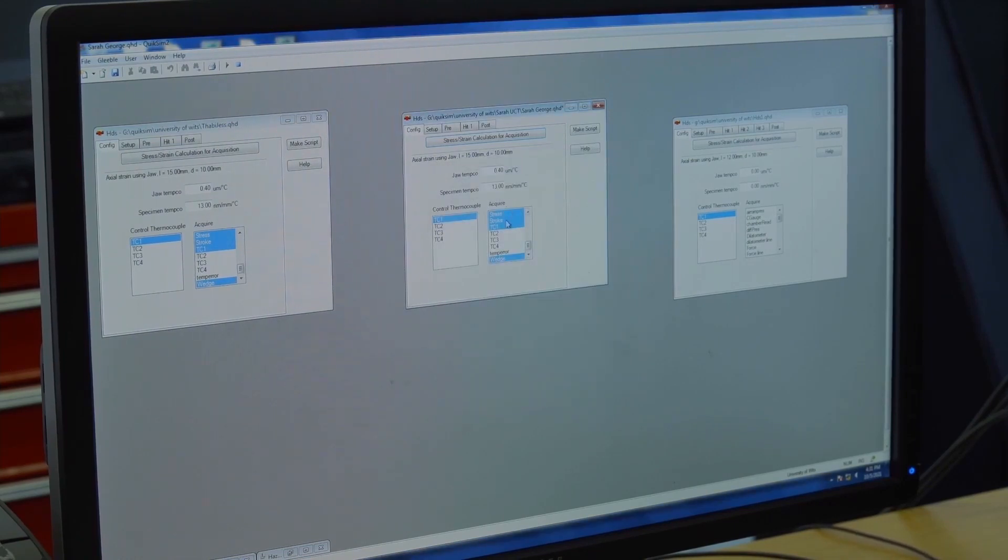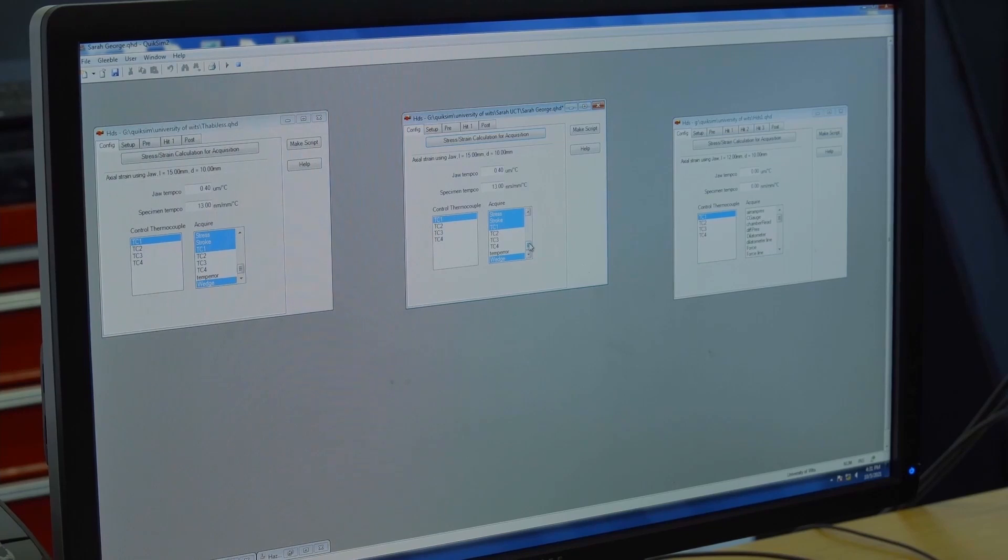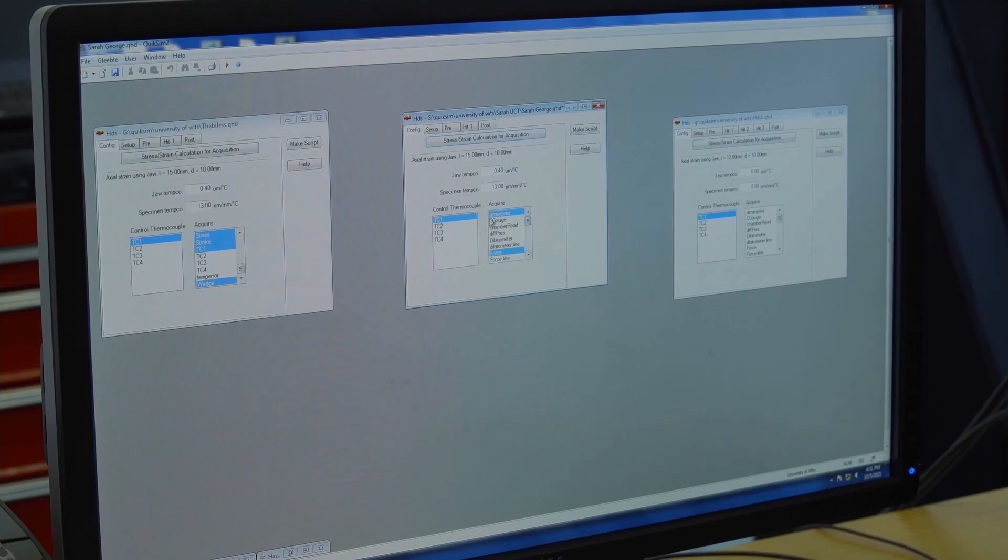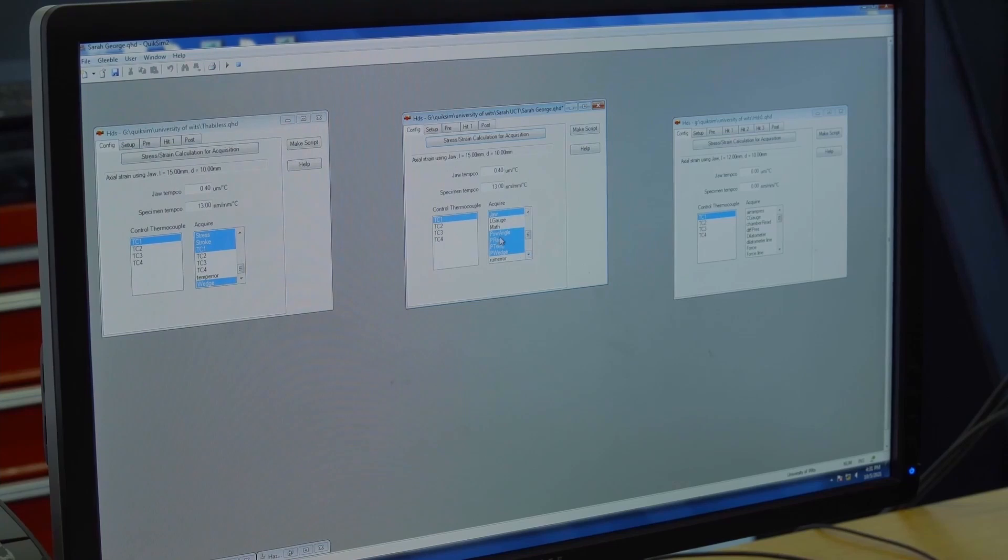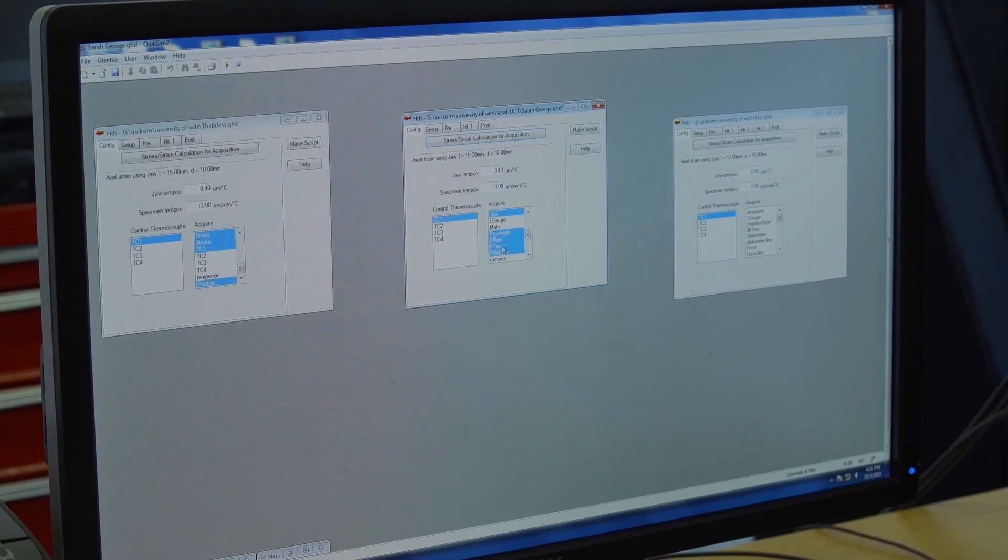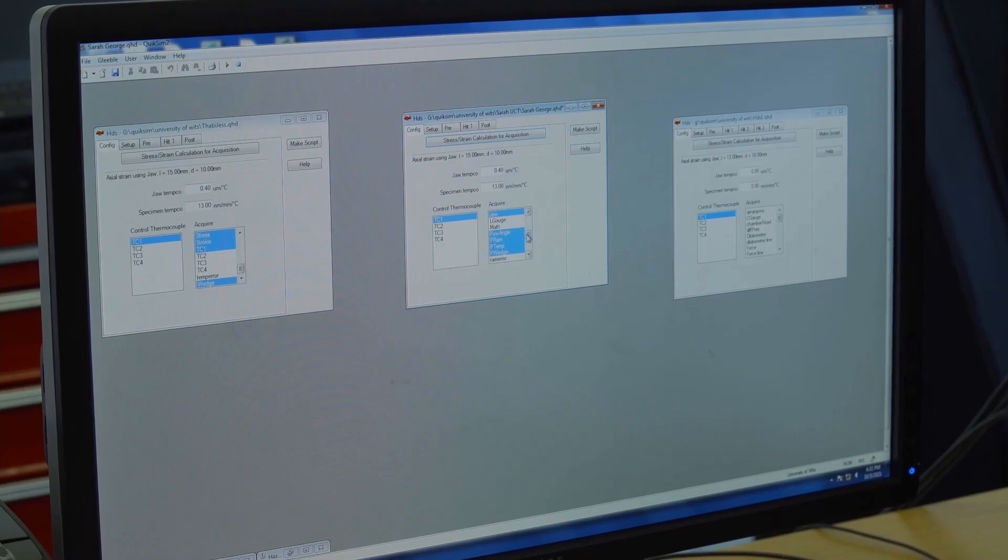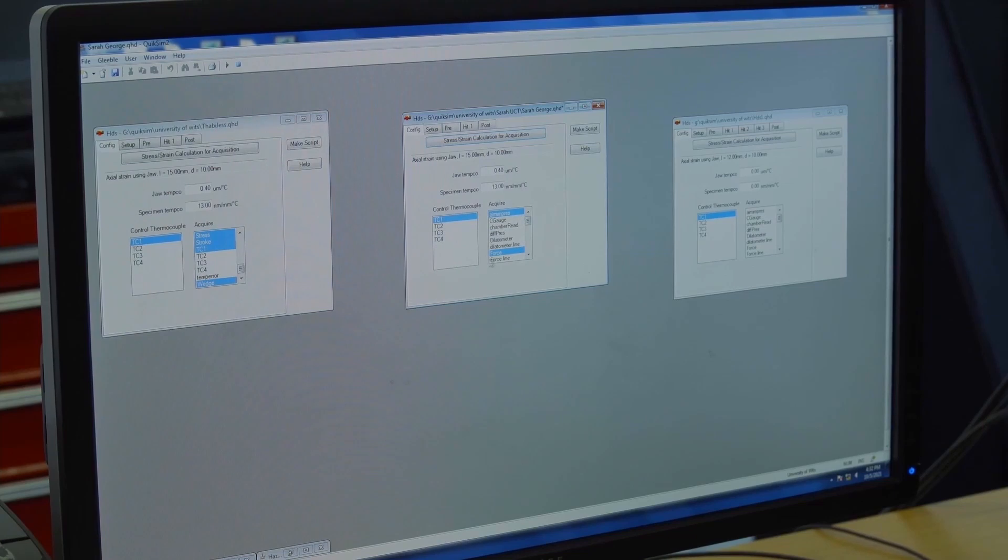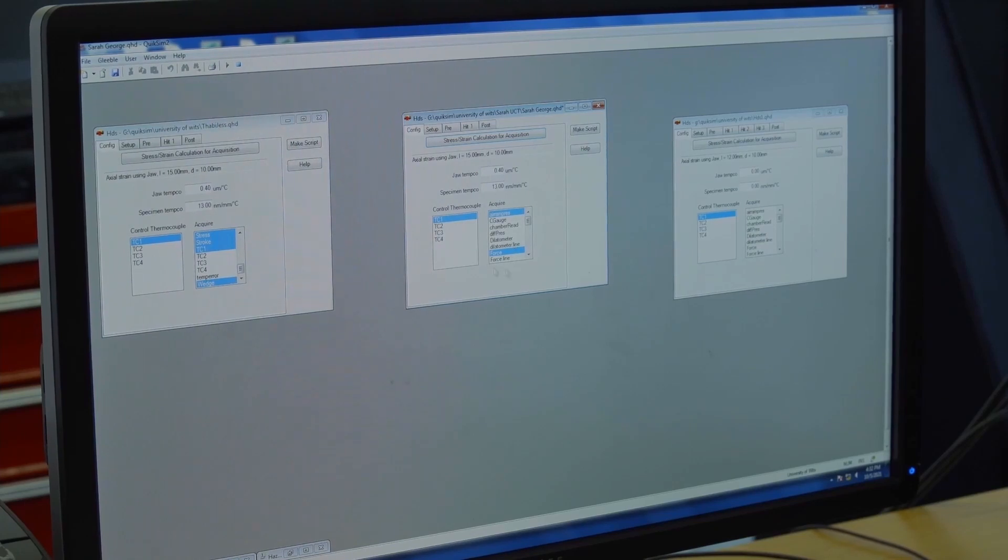Here you see acquire. The acquire is telling you to pick the results you want to see during the test. You are telling the Gleeble, acquire all this information during the test. We've acquired stroke, stress, TC1, wedge, air and pressure, the force, and quite a bit more. If you read the Gleeble application notes for flow stress testing, you already have information about what you should be acquiring.